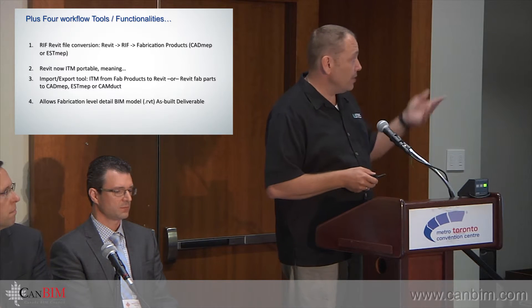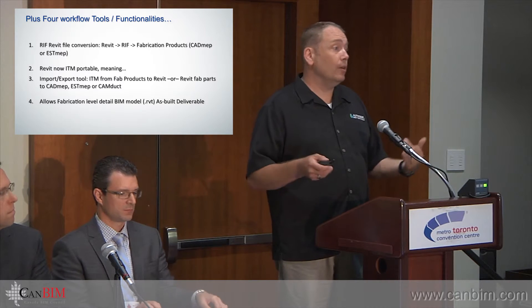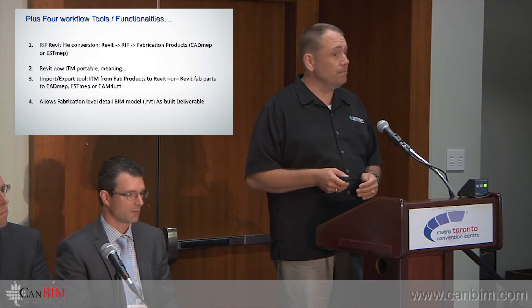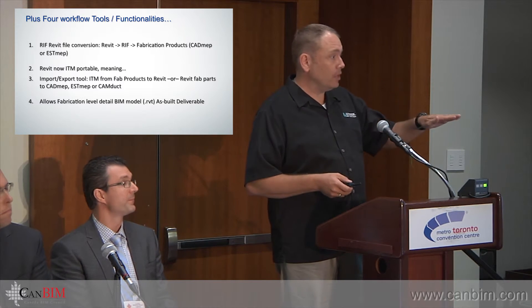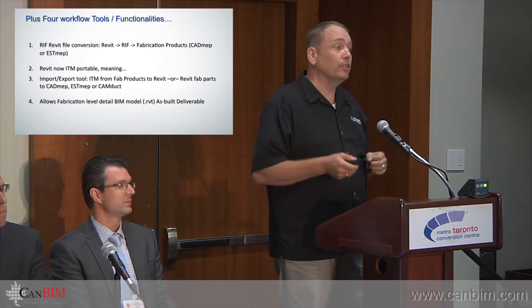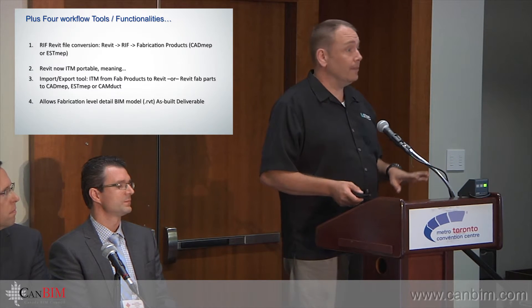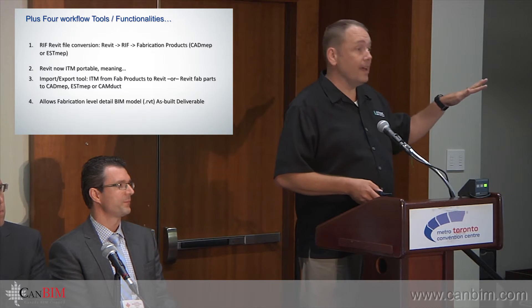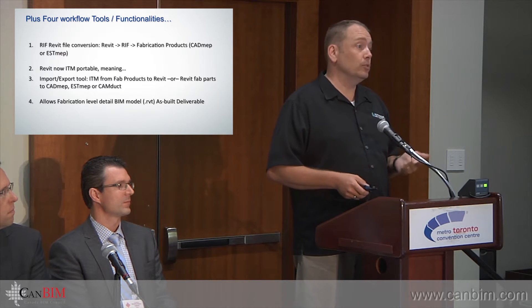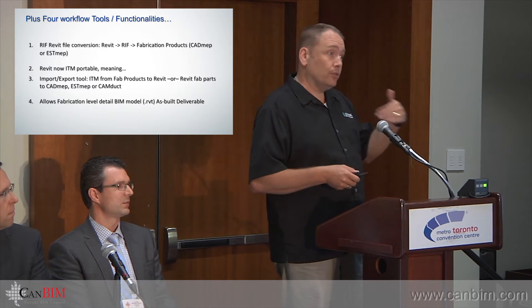This allows a fabrication-level detail model to be delivered. Can you start now in Revit as a fabrication-level tool? Yes, you can. Is it really ready for prime time in this first release? No. Because if you put in a piece of ductwork, you have to go to elevation view and pitch it, then continue stretching it — it's not really ready for that yet. But the groundwork has been laid, and that's what's key. The next release we're looking at making that better, perhaps using design line. We're also thinking about options for going from Revit to plasma cutting or from Revit to spooling — those are the next steps in the product.